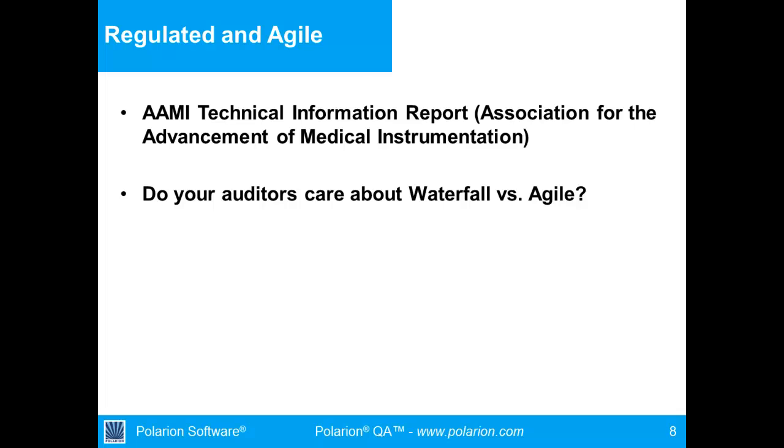But essentially it comes down to some simple recommendations where this group of thought leaders in the FDA world, along with the FDA people, have essentially recognized that agile values can actually be adopted into an FDA context, and that agile can work within quality management systems. But they had some particular points: if you're going to use agile and or exploratory testing, you need to have strong change management in that environment, and you also need to have a very functioning quality management system that the agile testing environment lives inside.